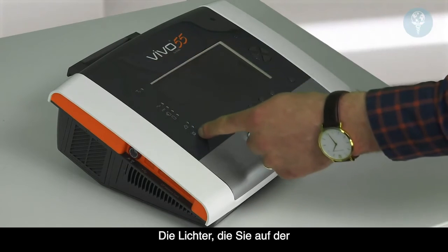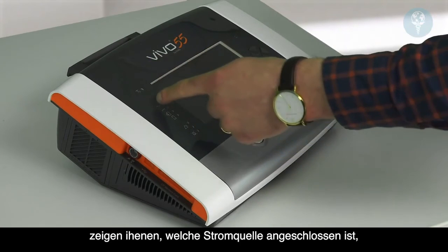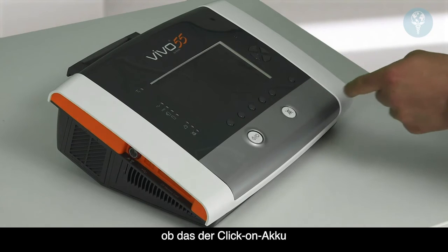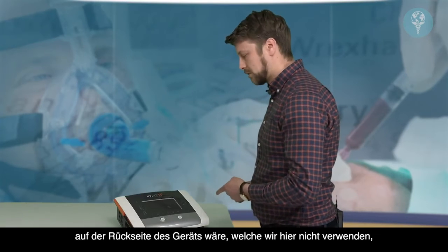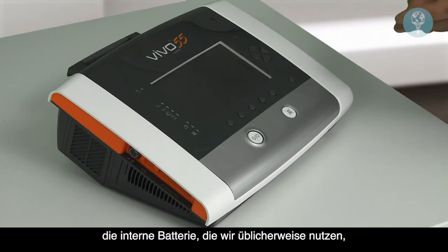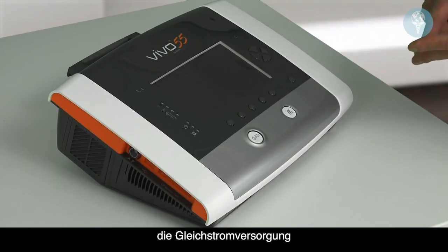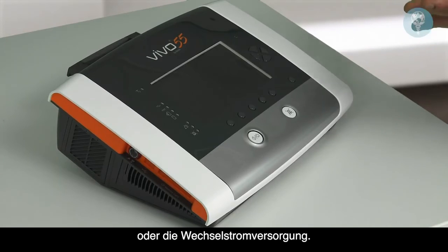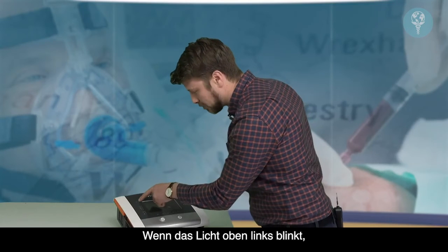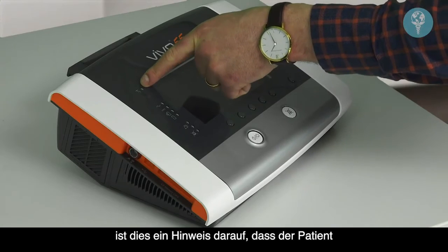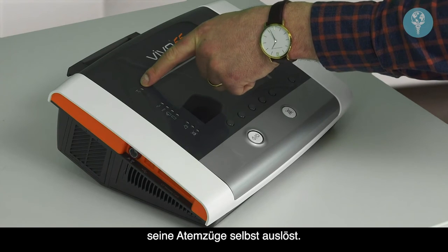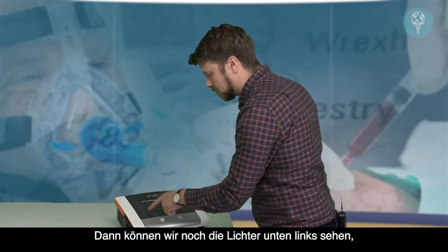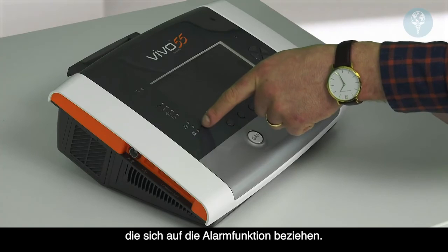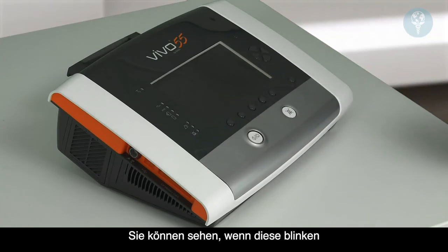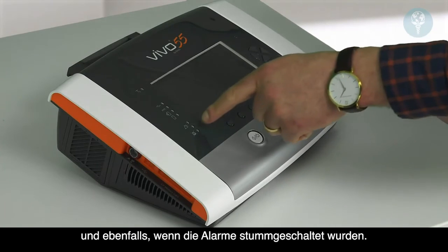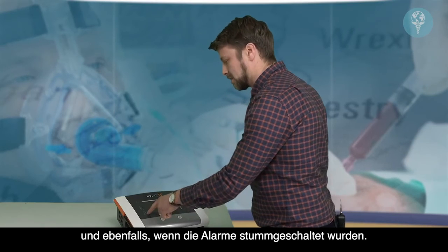The lights that you can see down the left-hand side of the interface will show you what power supply you're attached to, whether that would be the click-in battery on the back of the device, which we're not using, the internal battery, which you may be using, the DC supply or the AC power supply. So the light on the top left, when that is flashing, that's an indication that the patient is triggering their breaths effectively. And then we can see the lights in the bottom left, which relate to the alarm functionality. So you can see when those are flashing and when the alarms have been silenced as well.